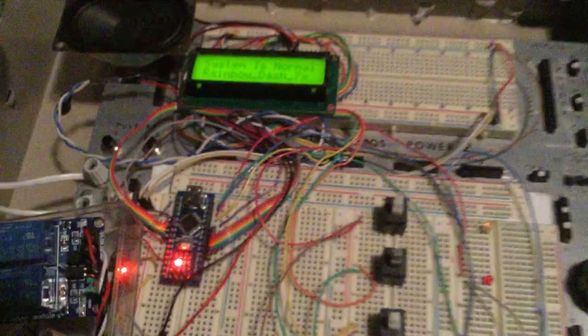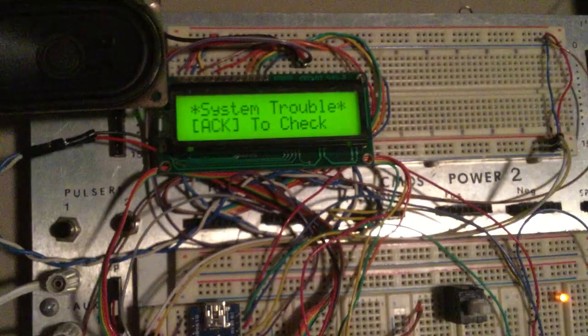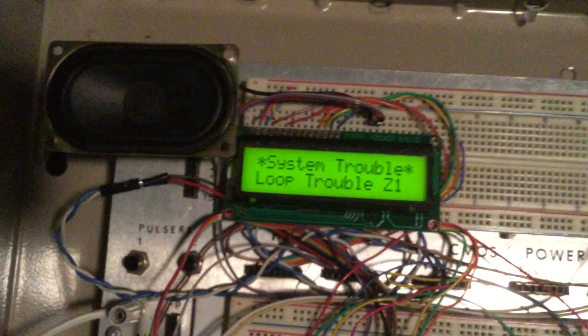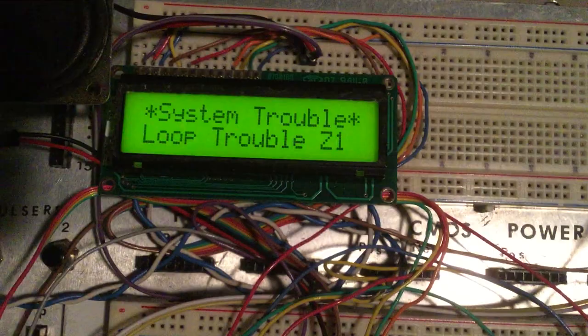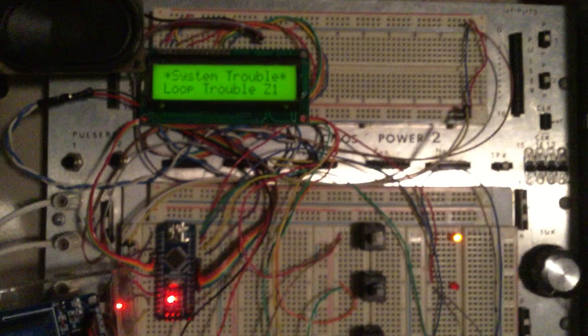So let's demonstrate the trouble first. So if I disconnect that, it will see system trouble, ACK to check. So I press acknowledge. We have loop trouble on zone 1. This is a 3-zone panel. However, I have not coded for zones 2 or 3 yet. Just zone 1. But in the future, that will show the zone in trouble. So now if we reconnect it, it will not clear until we reset. So let's reset. And here's all the trouble LEDs on. So let's reset it.